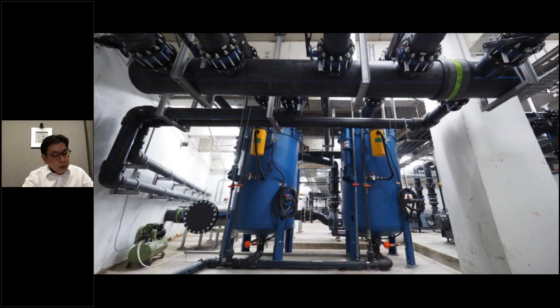Then the chemical clean. About what Adam said, about 1 year, we actually encountered one project in Johor. 8 years they've been using Defender filters, and they never did any cleaning. So we went in and found that they hadn't done any cleaning. What we did was one clean, only out of six filters. So only one filter, that's it. We checked the rest of the filters, the other five, and there's no issue. They're all working perfectly well.